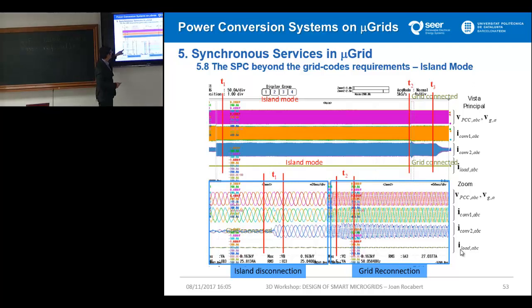Okay, the SPC immediately after that small transient that it's difficult to see, not because the image is small, but because the transient was very small. Okay. We get after some very small transient, the SPC converter injects the necessary P and Q to restore again the voltage. Okay, and we get again this is the case when the main grid is restored again. Okay. We add a delta of frequency and we add a delta of amplitude to the SPC in order to be synchronized again. And we can close the switch and we are not going to get any problem.